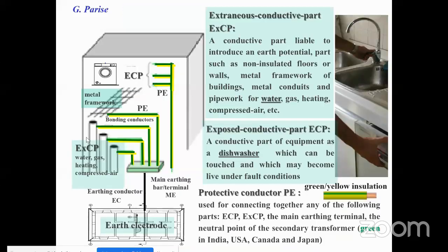So what is defined as an extraneous conductive part? A conductive part liable to introduce an earth potential, such as non-insulated floors or walls, metal framework of buildings, metal conduits, and pipework for water, gas, heating, compressed air. Exposed conductive parts are conductive parts of equipment, such as a dishwasher, which can be touched and which may become alive under fault condition.